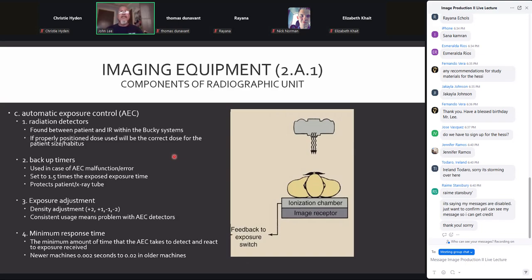Either an increase or decrease. The minimum response time. This is the amount of time that it takes for the signal from the detector to get to the machine and for it to react and say, okay, cut X-ray production. Remember that all of this is determined by electrons moving through conductors. And since electrons are physical pieces of matter, and the conductors are physical pieces of matter, there is an amount of time that it takes for the signal to travel from one area to another. It doesn't happen in an instant as it would with light.